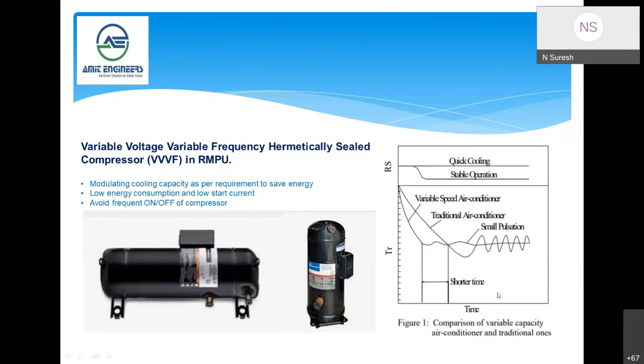The horizontal compressor, as briefed earlier, I have given the graph here, a comparison of variable capacity air conditioners and traditional ones. There is a modulating capacity as required to save energy. I hope there will be a doubt about how it is going to save energy. Say for example, the maximum designed condition power consumption of the compressor is 5 kilowatt, when the cooling requirement is less. This compressor is operated using PID control, based on the return air and supply air delta T, and the compressor will be run in variable frequency.